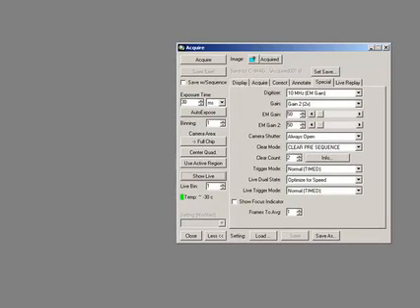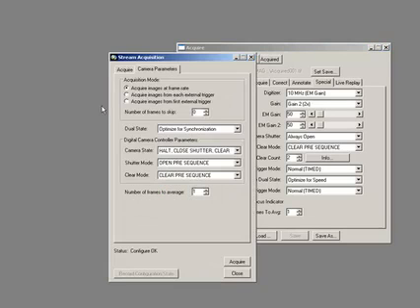Let's just stop the live preview for a moment and then come over here to our options for streaming acquisition. And if I ask for, let's say, 150 images, I'm going to assume that I'm going to get 30 frames a second out of this, so this should be 5 seconds worth of data that I'm going to acquire. And I've set it to stream to RAM. Under camera parameters here, I've got an option for dual state in terms of optimize for synchronization or optimize for speed. Given that we want to get 30 frames a second here, I'm going to choose optimize for speed as my settings, and then I've got my clear mode set to clear pre-sequence.